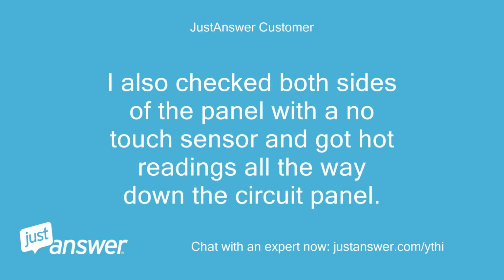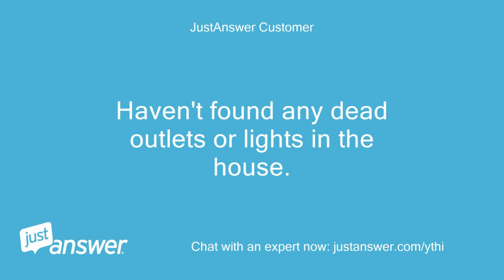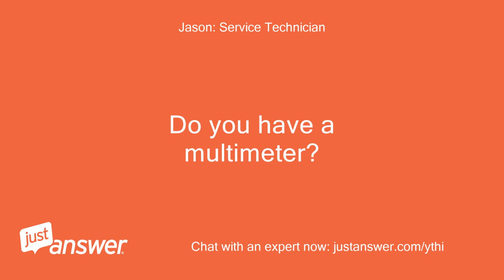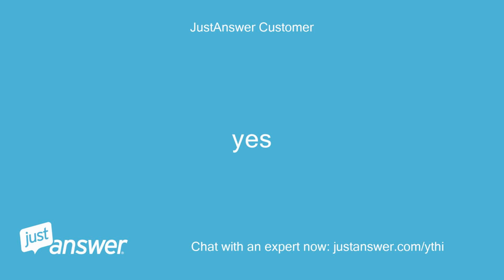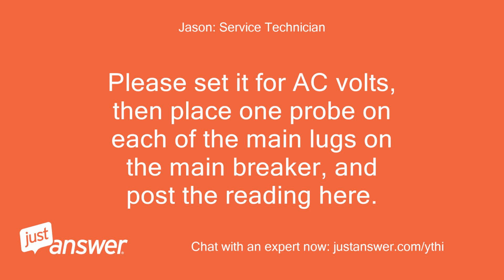I also checked both sides of the panel with a no-touch sensor and got hot readings all the way down the circuit panel. Haven't found any dead outlets or lights in the house. Do you have a multimeter? Yes. Okay, great. Please set it for AC volts, then place one probe on each of the main lugs on the main breaker and post the reading here.